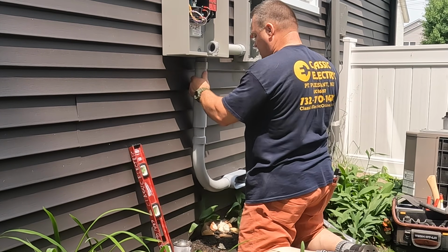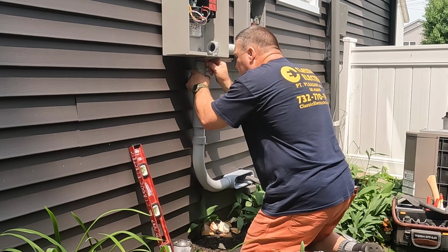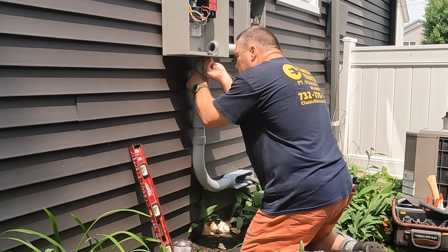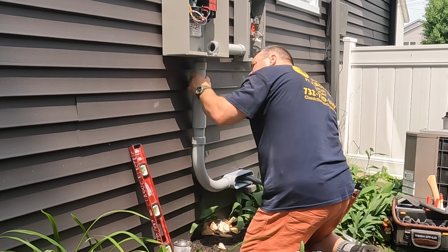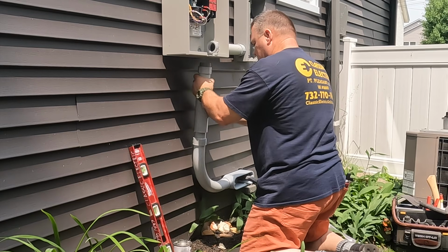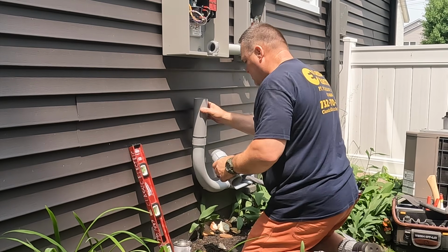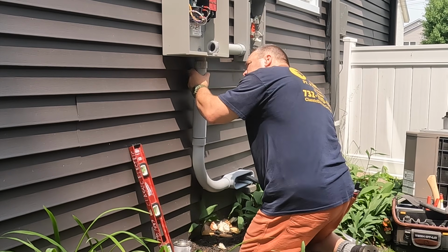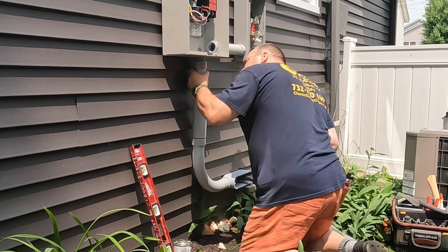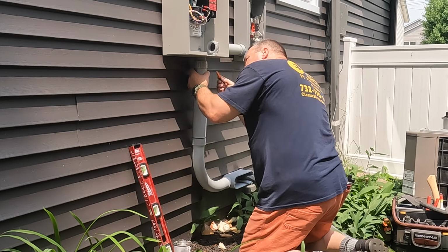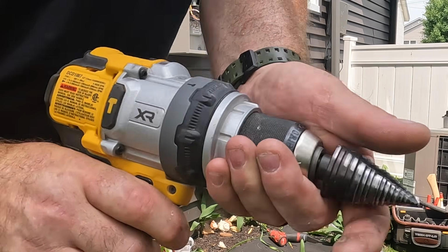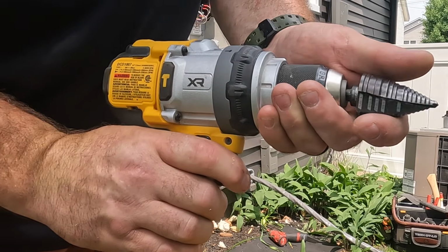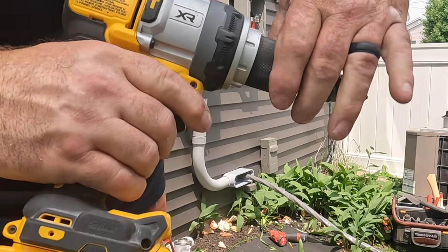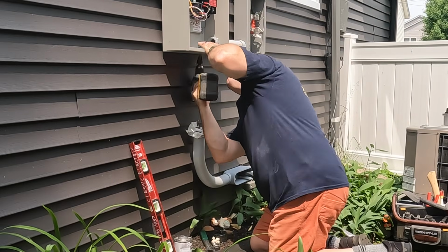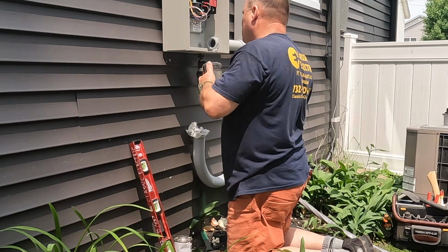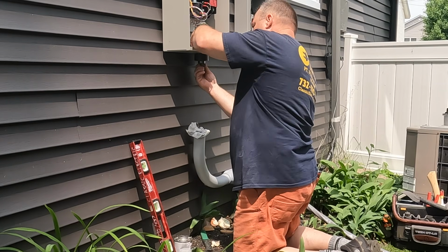All right, anyway, here I'm using, as you can see, the 2-inch PVC LB and the 2-inch PVC sweep, and then I'm using an expansion coupling to make it easier for me to get this male adapter into where it needs to go. It's also going to accommodate any expansion of that PVC from hot temperatures. It's also going to tell me where to make my hole in the transfer switch for my load that goes down to the electrical panel in the basement.